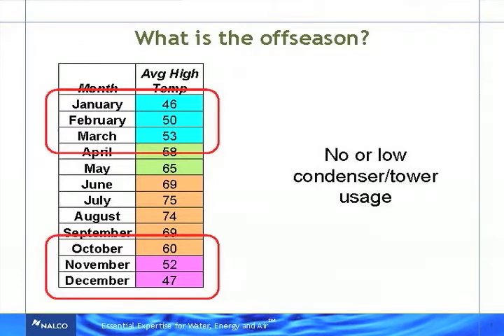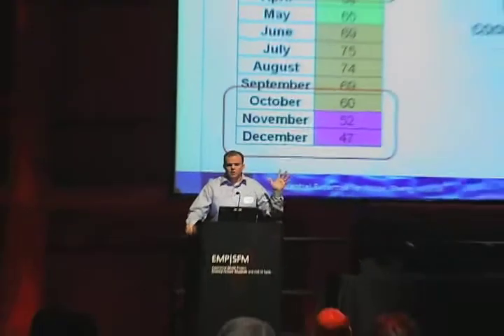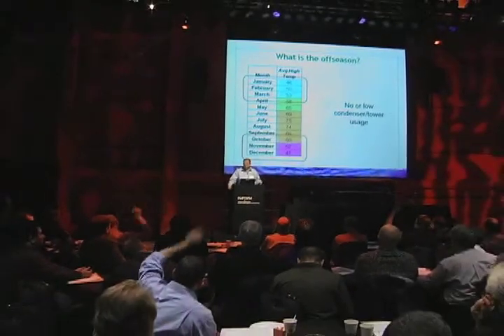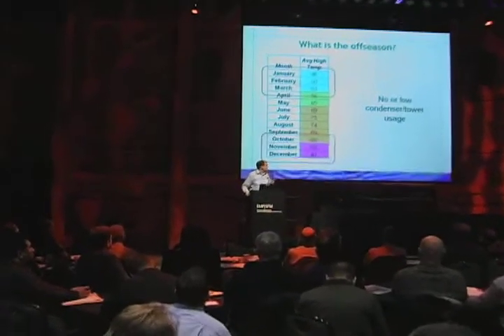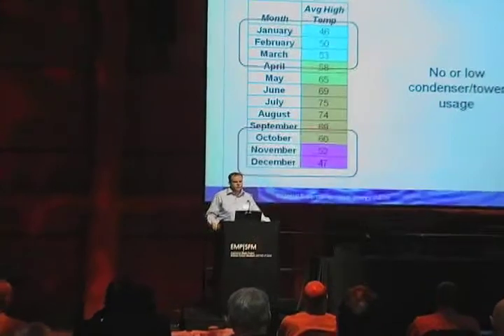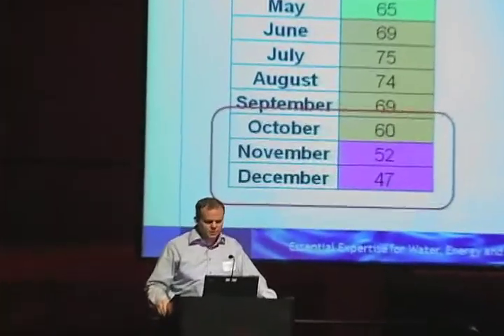Historically, a lot of people used to just shut their cooling systems off in the wintertime, but now with data centers, free cooling, all those kinds of things, more and more I see people keeping them online just in case, or keep them online because they have to. Raise your hands if you keep your system either filled or running in the winter, and mostly because of data centers, I'm assuming, or the load's still there even in the cold months. So that's what I'm talking about, the off-season during the low or no condenser usage periods.